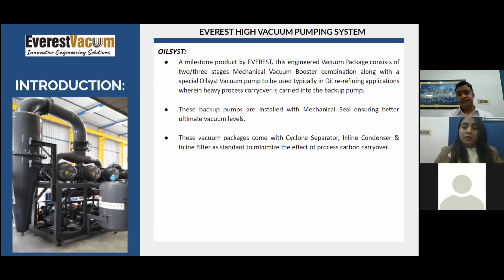We also have an inline filter and a condenser to stop carryovers escaping from the pre-condensers or partial condensers installed, in order to improve the efficiency of the pumps - since during compression we need to maintain some clearances. So to avoid obstructing the operation of the machine, we use these filters and traps.